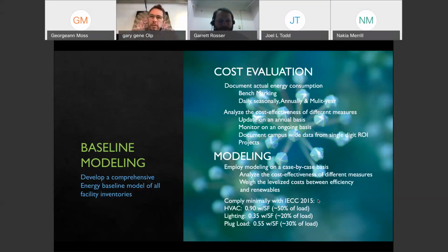And down here we've got some goals, based on a 25,000 BTU per square foot goal on an all-electric building, where things might come out. Your buildings will be different, but for Dallas College we're looking somewhere in the 1.6 to 1.9 watts per square foot as an average monthly demand, with different distribution of HVAC, lighting, and plug load on different buildings.